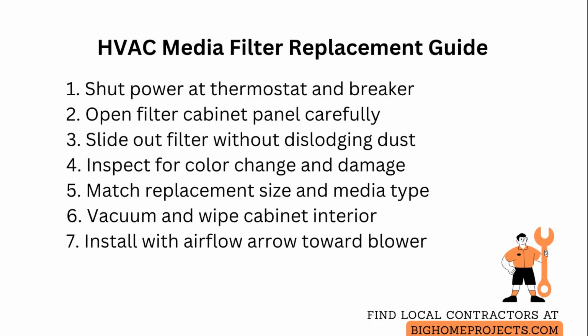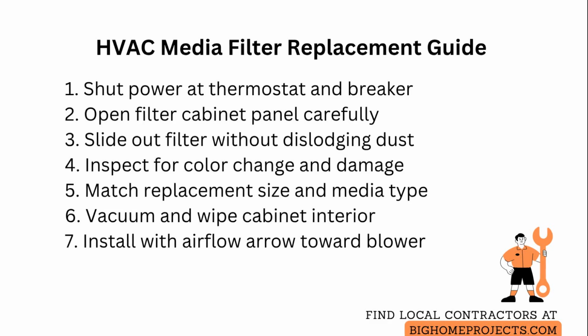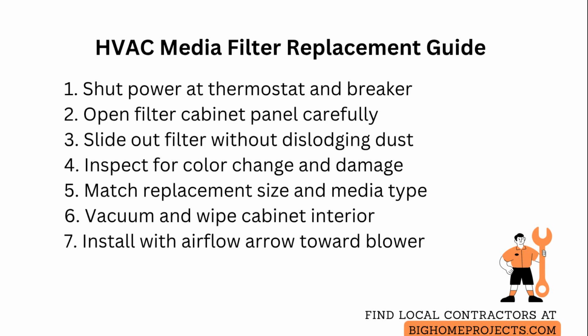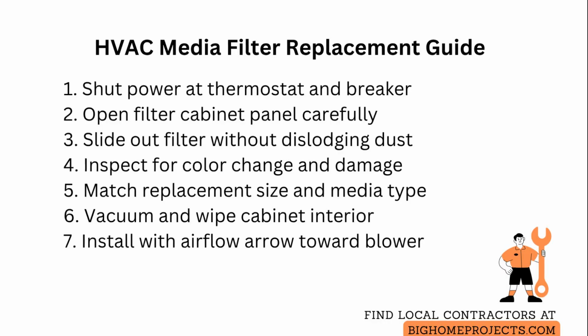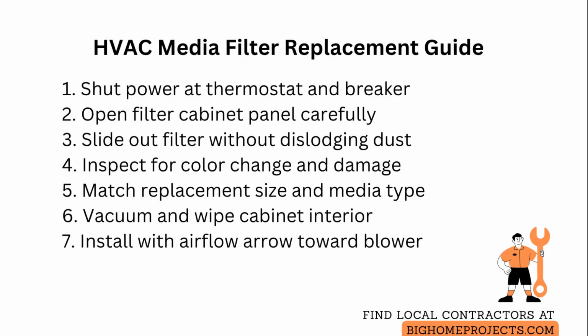Before inserting the new filter, vacuum the filter cabinet interior and wipe any loose dust from the frame and nearby coil access area. Then install the media with the airflow arrows pointing toward the blower, seating the frame fully to prevent bypass.